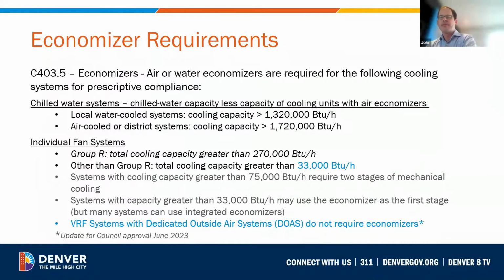Economizers are a prescriptive requirement carried over from the 2019 Denver Energy Code. The requirements for chilled water system economizers have not changed. However, for individual fan systems, especially for packaged equipment, the cooling capacity which triggers the requirement for an economizer in buildings other than Group R has been reduced to 33,000 BTUs per hour. Given that economizers are a prescriptive requirement, a project may pursue a performance compliance pathway for a design without economizers.